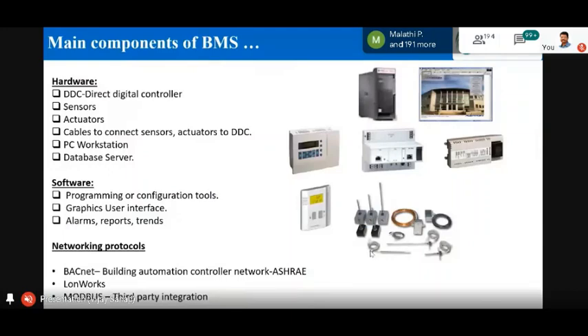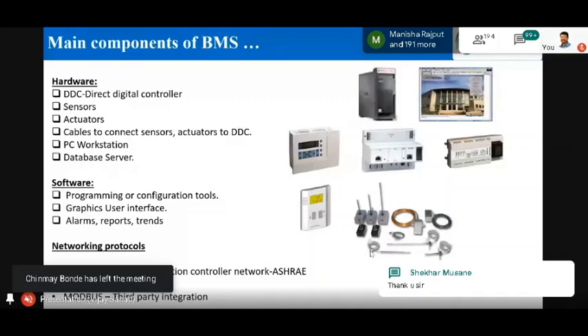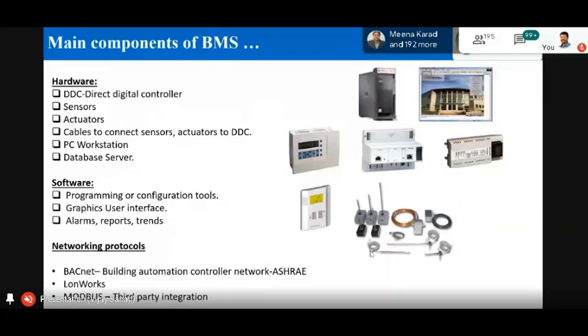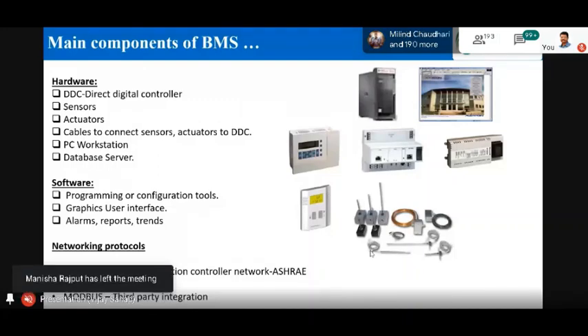So, it has a direct digital controller, which are actually mounted in the field. It has a distributed architecture. So, controllers are mounted in the field. Like if there is a huge campus, and if there is an AHU room, air handling unit room, you'll have a controller actually mounted in the AHU room. All the signals from the AHU are locally wired to the controller, and one cable will come from the controller to the control room where there is a BMS and the supervisory controller. And that is the reason this is called a distributed architecture.